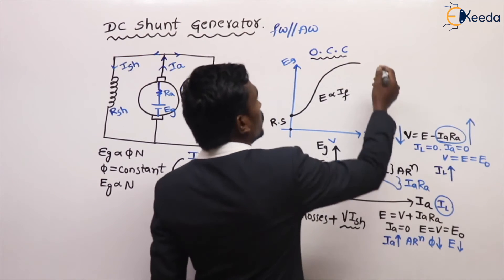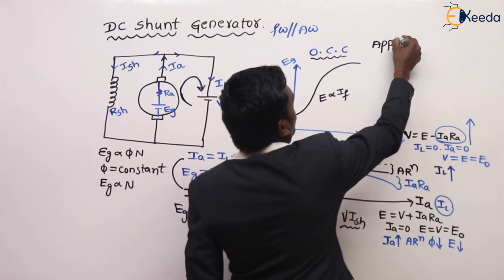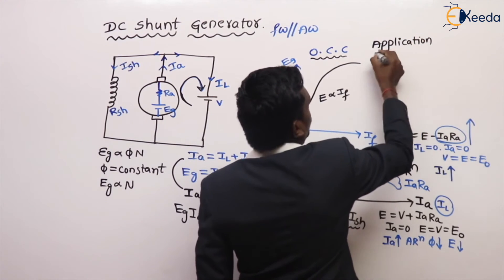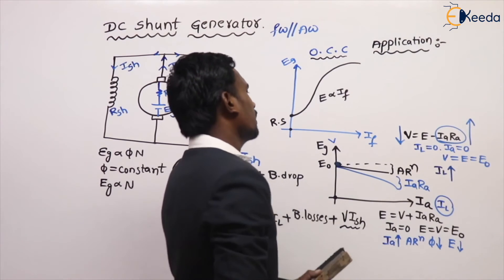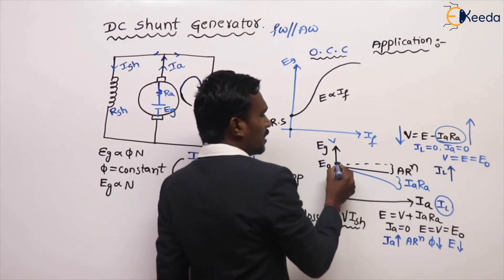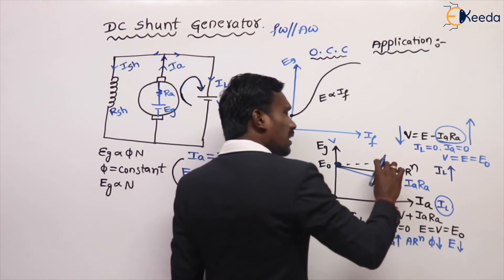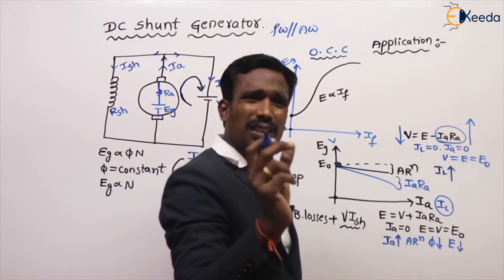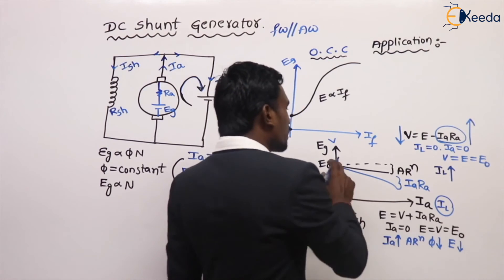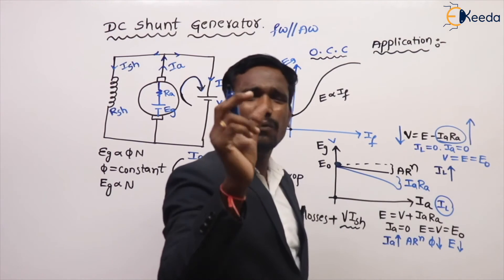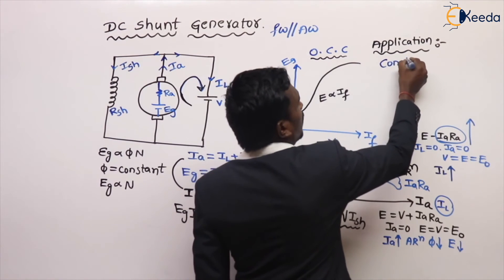What are the applications of the DC shunt generator? In the load characteristics, the load voltage reduces when load increases, but this decrement is very small — not even 10%, just around 5% only. That's why these generators are used for constant voltage applications.